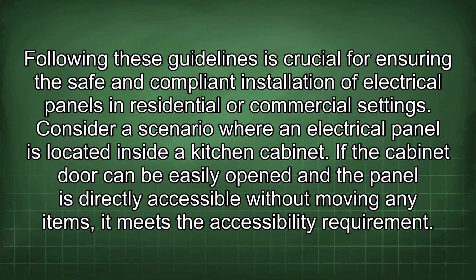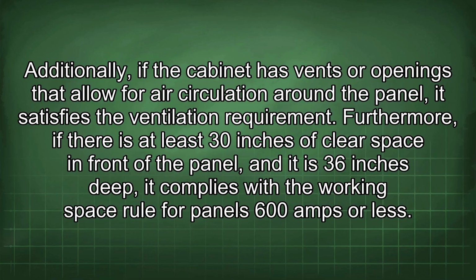Consider a scenario where an electrical panel is located inside a kitchen cabinet. If the cabinet door can be easily opened and the panel is directly accessible without moving any items, it meets the accessibility requirement. Additionally, if the cabinet has vents or openings that allow for air circulation around the panel, it satisfies the ventilation requirement. Furthermore, if there is at least 30 inches of clear space in front of the panel and it is 36 inches deep, it complies with the working space rule for panels 600 amps or less.